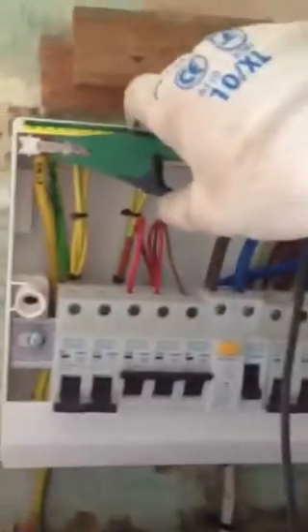Always a little bit of a difficult job. Okay, make sure that's nice and tight. Next test for us to carry out is the prospective earth fault current. With this tester I don't need to alter anything at all. I just put my crocodile clip onto the main earthing terminal again.